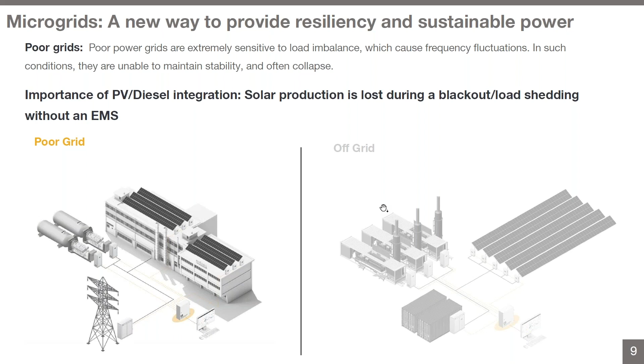What most people don't know about having solar power on this type of system is that with load shedding or blackouts happening, you will actually lose your solar production during these times, because the PV inverters will shut down to protect the grid and prevent power from going in reverse. That's the real value that Elum's hybrid controller and EMS bring to this type of grid and context.